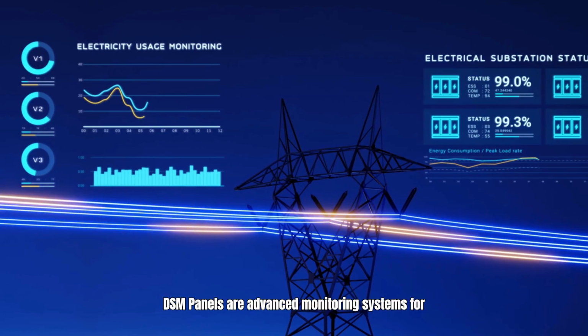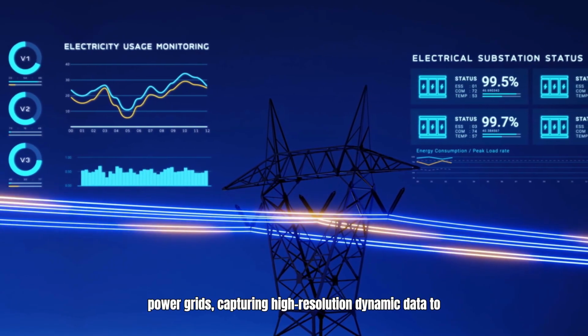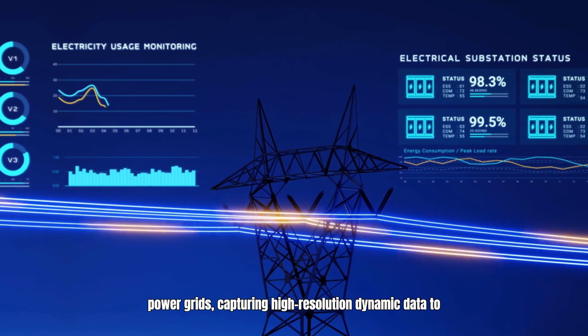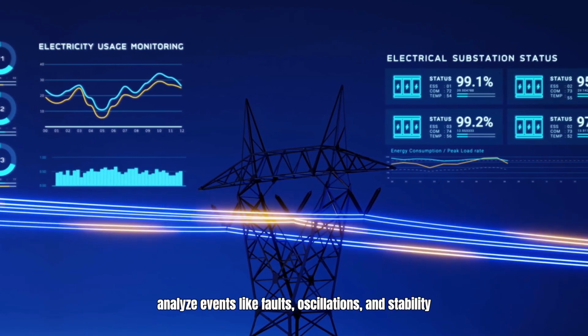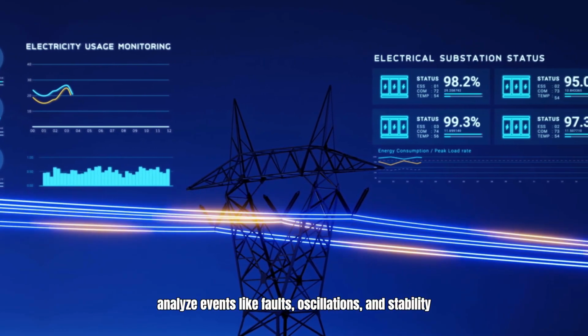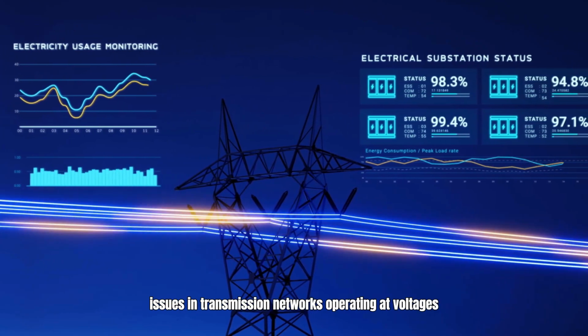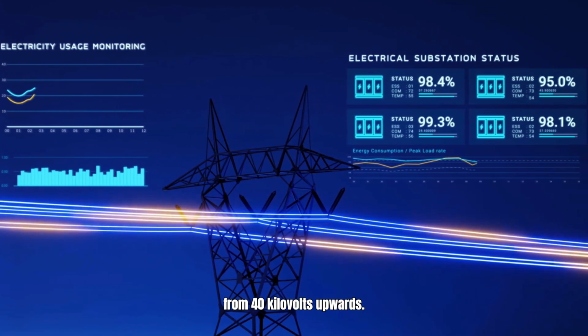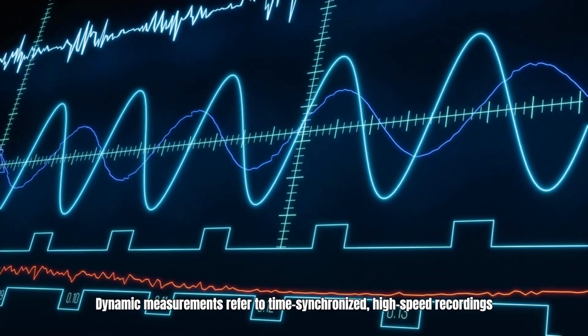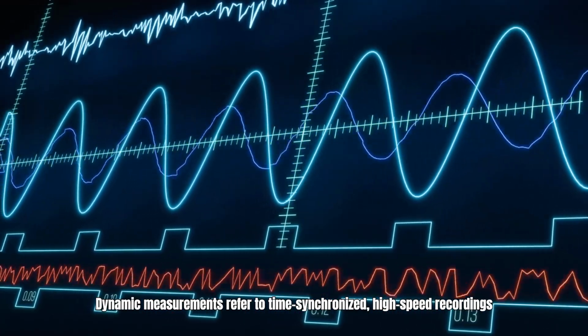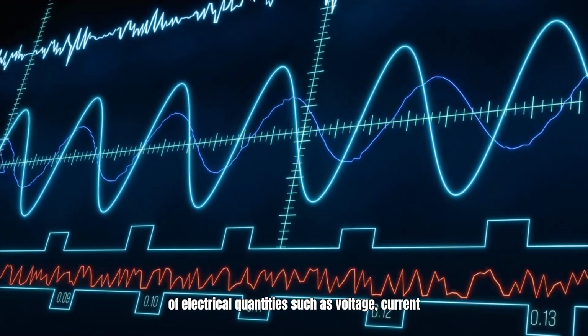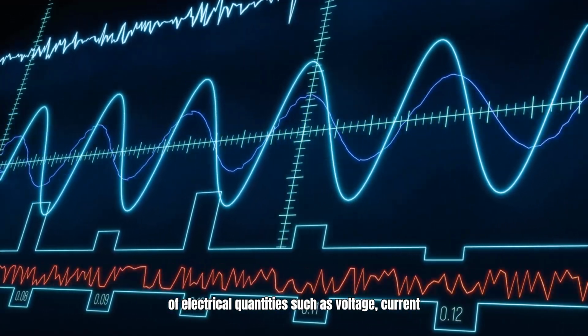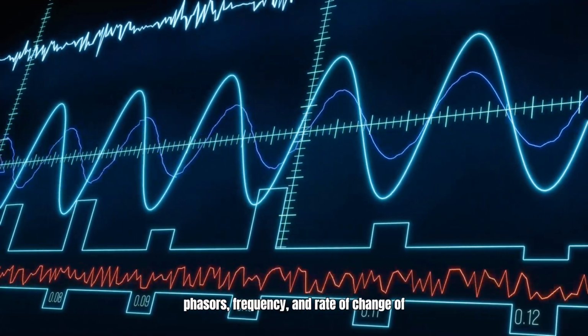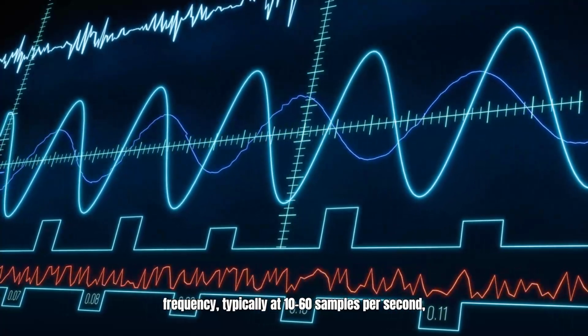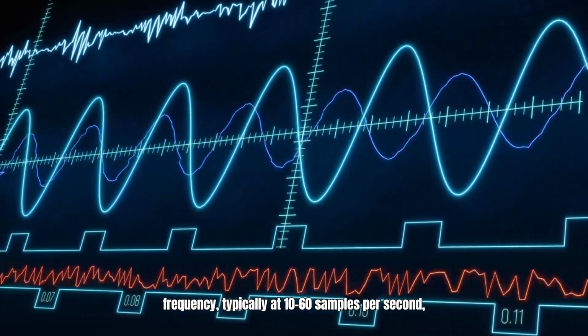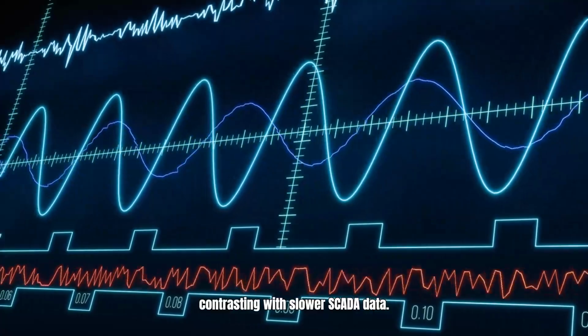DSM panels are advanced monitoring systems for power grids, capturing high-resolution dynamic data to analyze events like faults, oscillations, and stability issues in transmission networks operating at voltages from 40 kilovolts upwards. Dynamic measurements refer to time-synchronized, high-speed recordings of electrical quantities such as voltage, current phasors, frequency, and rate of change of frequency, typically at 10 to 60 samples per second, contrasting with slower SCADA data.